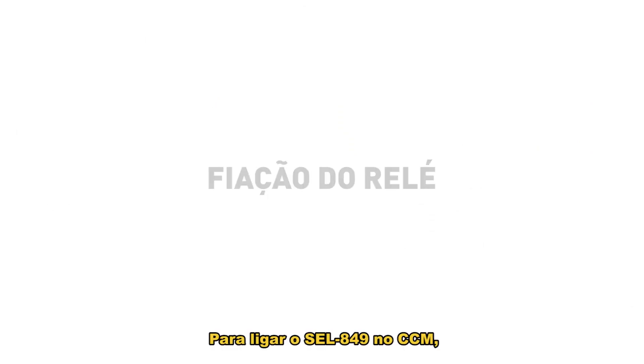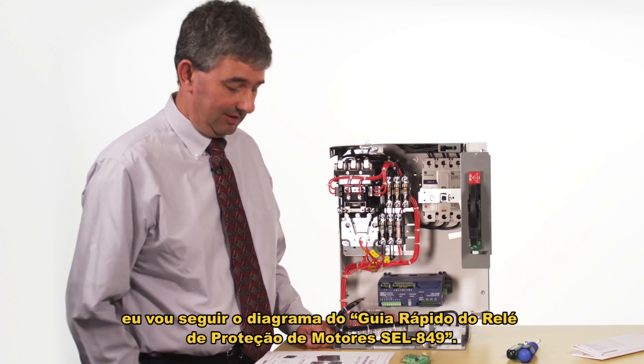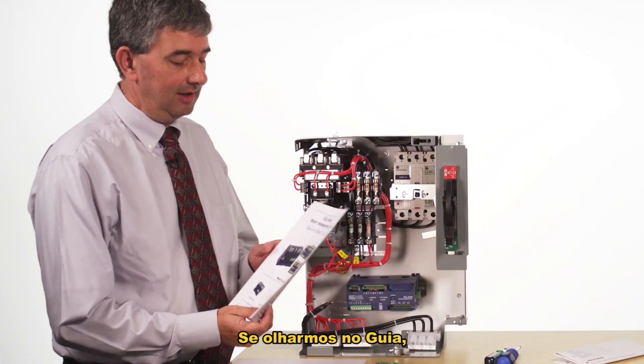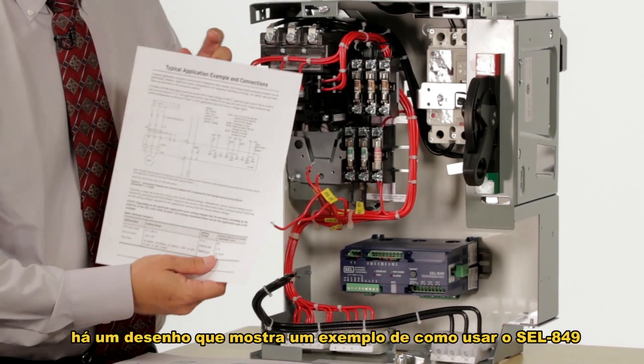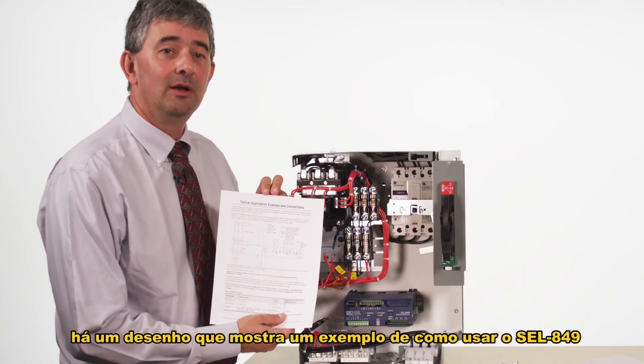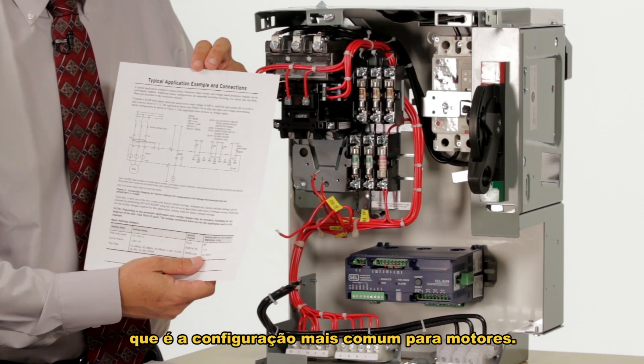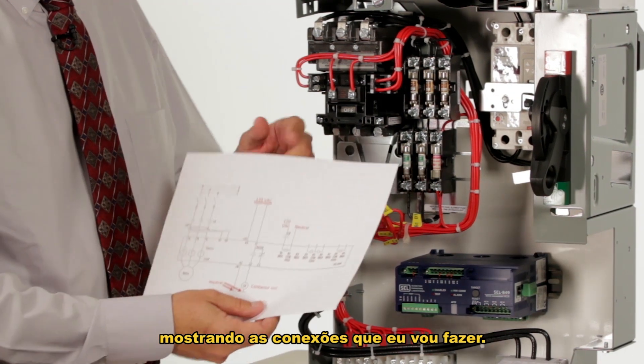To wire the 849 into the motor control center I'm going to follow the diagram given in the SEL-849 motor management relay quick start guide. On the second to last page there's a drawing showing an example of how to use the 849 with a full voltage non-reversing starter configuration, which is the most common configuration for motors. I've made my own simplified version of this drawing showing the connections I'm going to make.